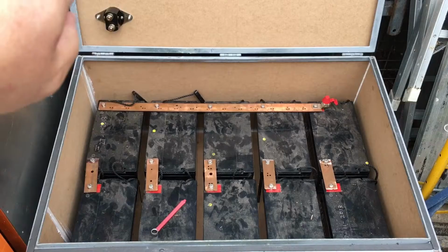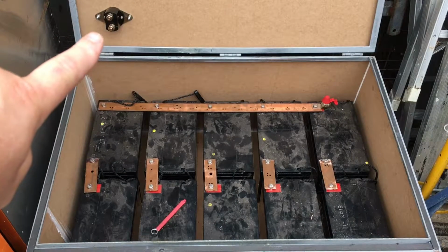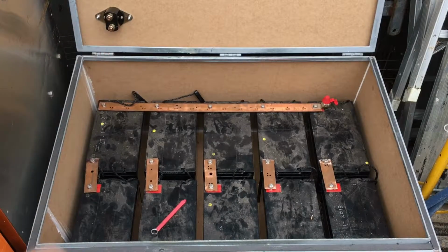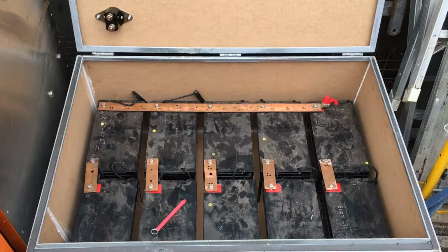Up in the top corner is a 24 volt external isolator with a key. So when the box is closed, the isolator's on the outside. Should there be any problems, someone could come and take the key out, isolating the power from the batteries going to the switchboard.